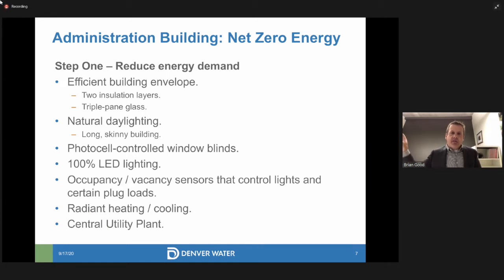The southern side of the building has photocell-controlled window blinds, which automatically come down during the day to reduce glare and heat. All of the lighting, both inside and outside the building, is LED on campus. We have occupancy and vacancy sensors that control lights and certain plug loads. So for most people, they plug their computer monitors into these, and if there's nobody on the floor, it shuts those monitors completely off. Hopefully my lights don't go off during the talk, and if so, I'll wave my arms.